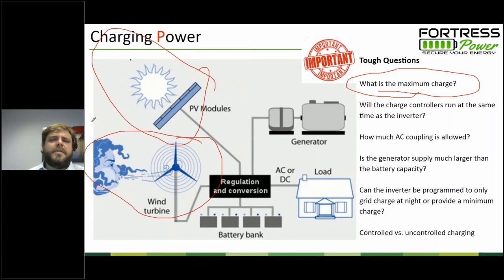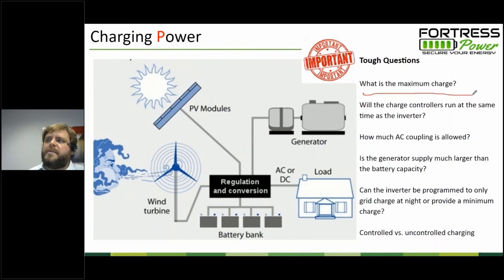And so some questions to better understand your system: what is the maximum charge that's going to be placed on the battery? If my generator is substantially larger than my battery inverter system, if I'm running a 5 kilowatt critical load panel with my battery system and I have a 20 kilowatt generator, how is the charge to the battery going to be regulated? Normally it's with an inverter charger or battery charger so that it is regulated. But I guess the key takeaway to think about is: is the battery going to be charged by more than one charging resource at the same time? If so, what is the combined total of all those charging resources together? And is that within the regulation of the battery? Or do I need to do some things to prevent these charging loads from occurring at the same time?